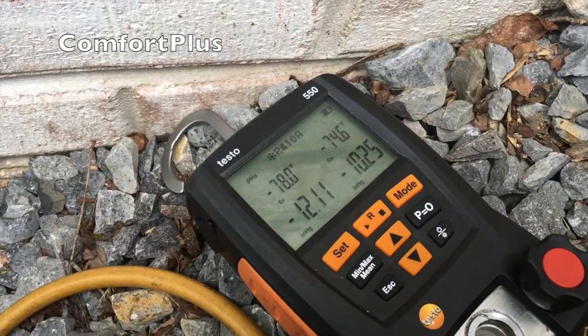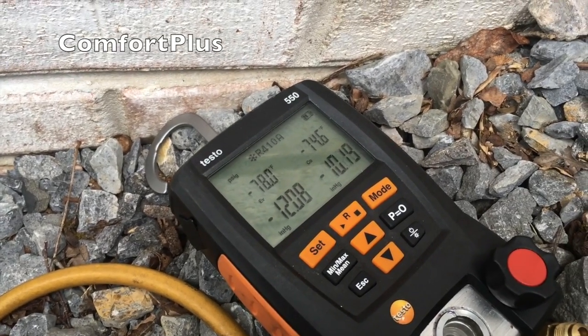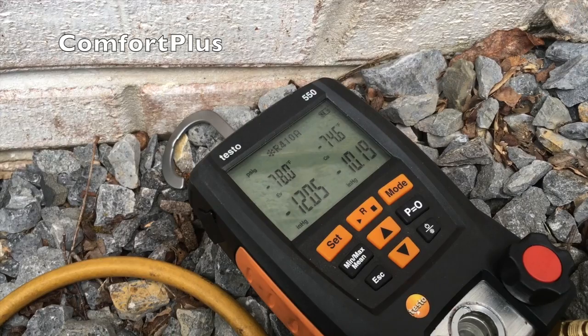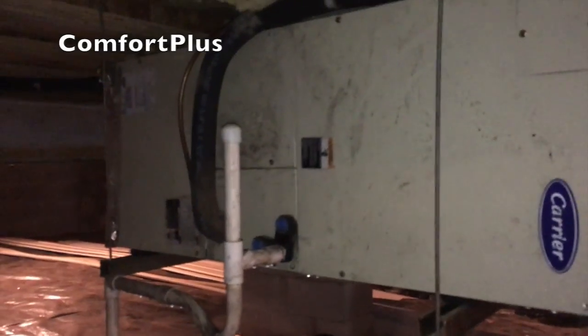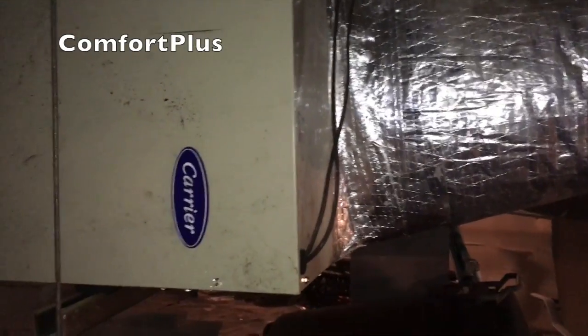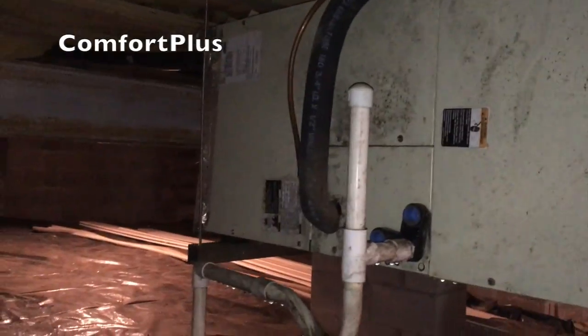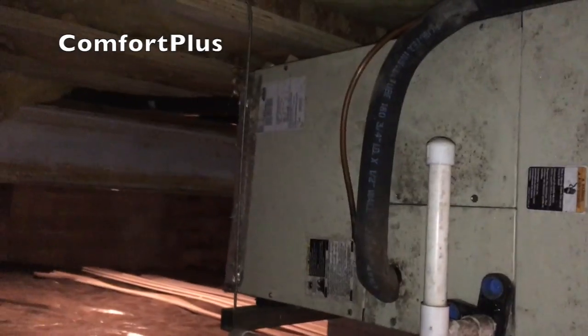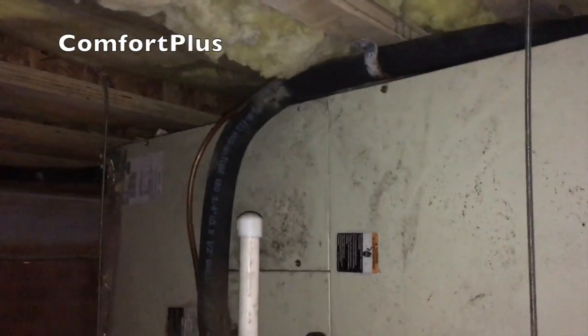Okay, she pumped down into a vacuum, so I've got the king valve sealed off. I can go inside now and cut the air handler loose. Okay, here we are in the crawl space. What we're going to do is cut this one loose. There should be a seam right there between the 10 by 16 duct and that transition fitting. So I'll take the ductwork loose at that seam. It's got a little 12-inch flex running around the back that's tied into the end. I'll take it off, cut the line set loose, pull the power out, thermostat wire out, and slide it out of here.